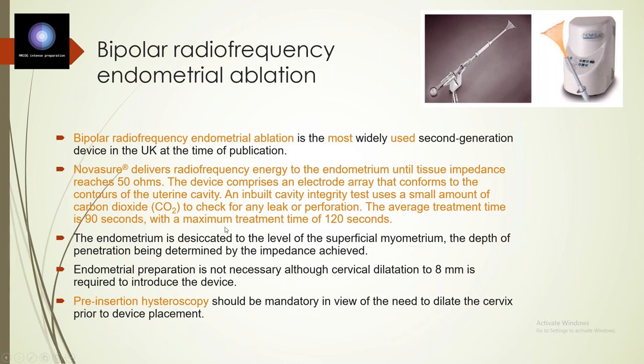The treatment cycle is only 90 to 120 seconds, so it hardly takes 2 minutes to cause endometrial ablation. The endometrium is desiccated to the level of the superficial myometrium. The depth of penetration is determined by the impedance achieved.